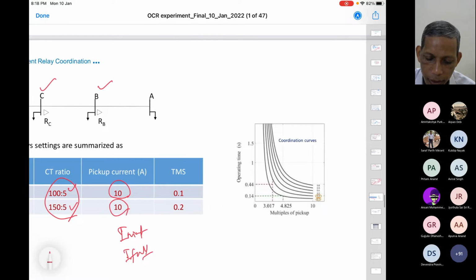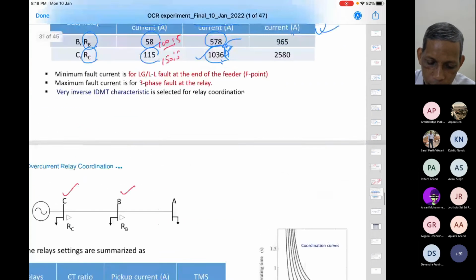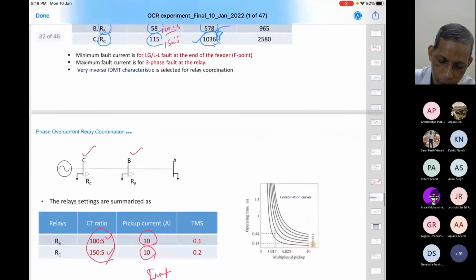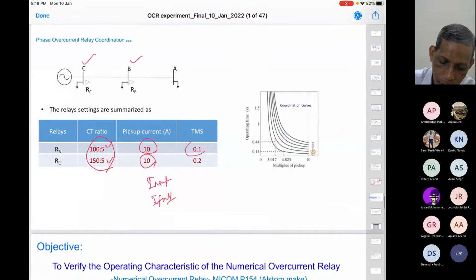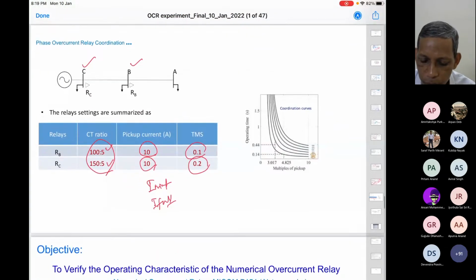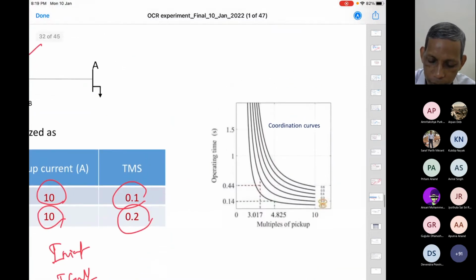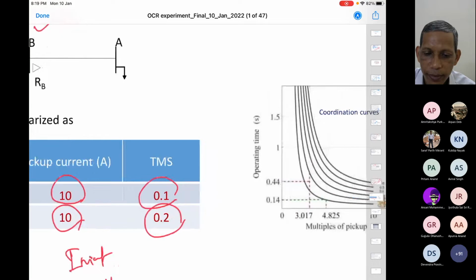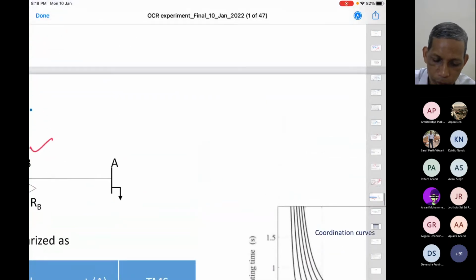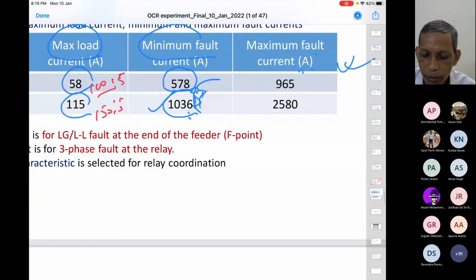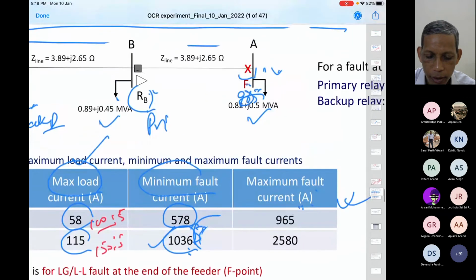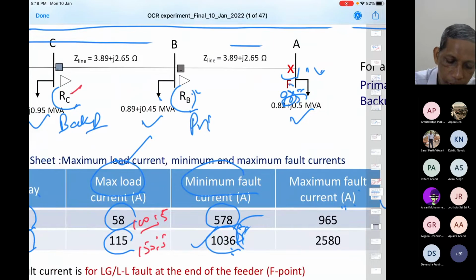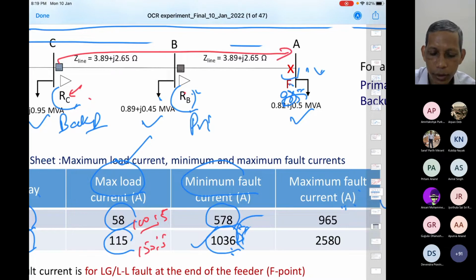Agree? And for this, the corresponding TMS is 0.1 and 0.2. How do we get 0.1 and 0.2? You see here, I'm explaining. So coordination time. From this table, maximum fault current. See, one point to clarify here: RC acts as a backup for RB. So the jurisdiction of RC is from here to here. The jurisdiction of RB is from here to here, up to this point.